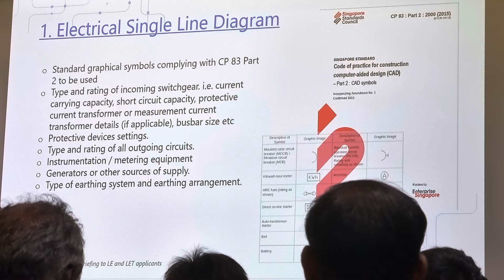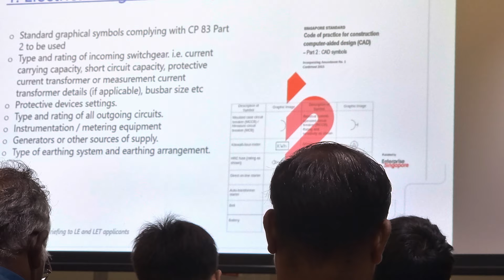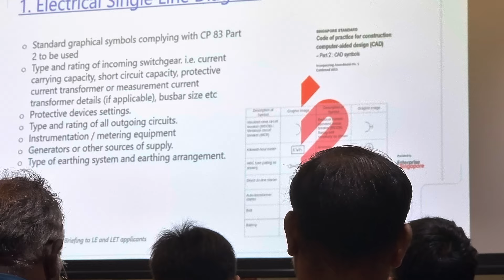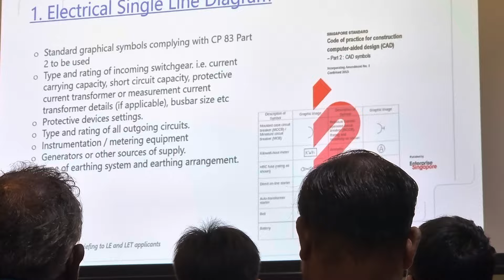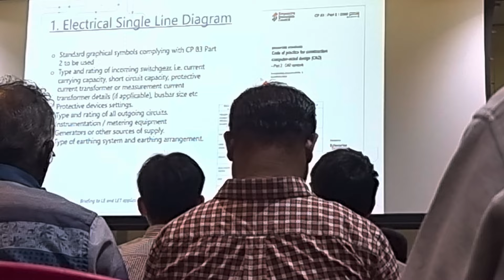So in the single line diagram produced during the interview, please follow the CP83 standards. What you need to show is the type and rating of the incoming switch, whether it's a circuit breaker, fuse, or MCB. You need to show the rating, the current capacity, the breaking capacity, and some protection devices, for example, a protection relay or an ELCB.